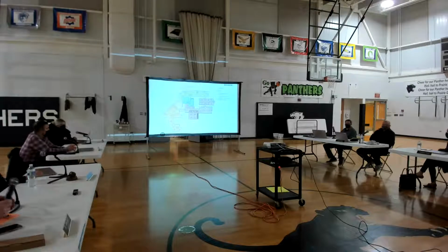I think what you're getting at is there are differences in how much space you need above the ceiling, to the roof deck, and for the structure. There's a potential advantage with geothermal or VRF compared to a standard air delivery system, which requires more depth because you're moving a lot more air volume.